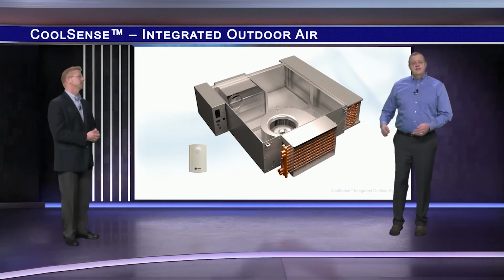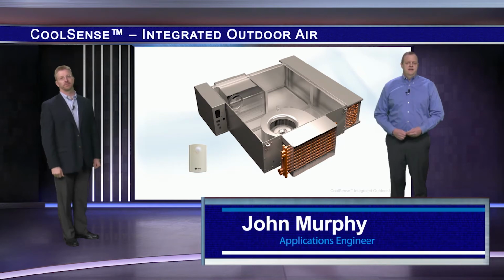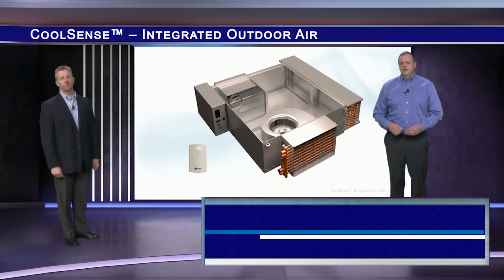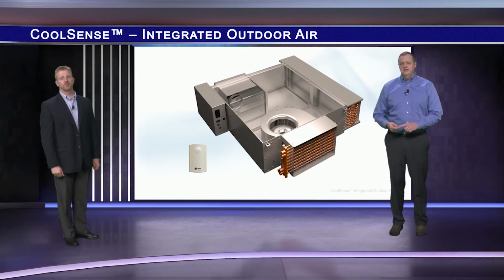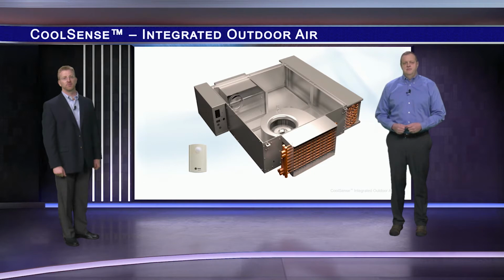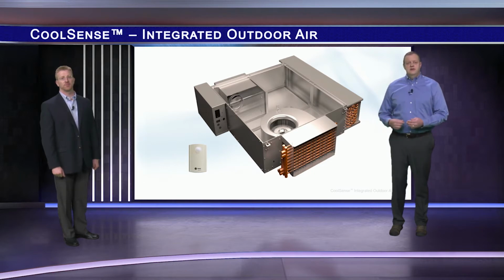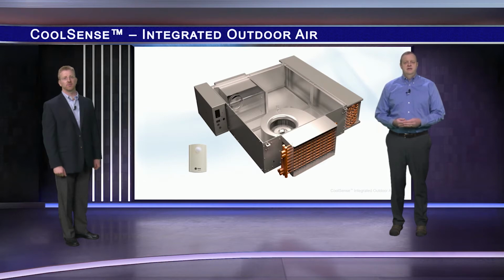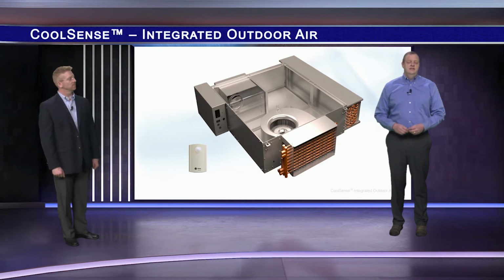As Ryan explained, this cooling coil is intended to operate dry. That is, no condensation. We ensure this by properly designing the dedicated outdoor air system to keep the space dew point low, and then also by controlling the temperature of water delivered to this coil so it's above that space dew point. However, each Trane terminal unit also includes a drip pan located underneath this coil in the event that unintended condensation does occur. In this drip pan is a moisture sensor. If condensation was ever to occur, this sensor would trigger the condensate avoidance sequence that's pre-engineered into our factory-mounted controller. I'll cover this in more detail in just a bit.